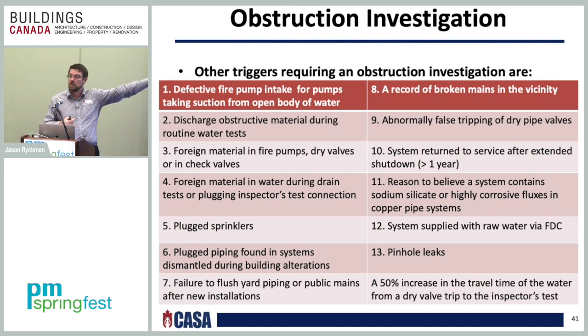If you have a record of broken mains within the vicinity of your building, that would be an obstruction investigation. Abnormally frequent false trip tests. So obviously with the dry system, if you have multiple trip tests for no apparent reason, that is a means of doing an obstruction investigation. System returned to service after an extended shutdown that is greater than 1 year, you have to do an obstruction investigation. Reason to believe a system contains sodium silicate or highly corrosive fluxes in copper piping systems. A system supplied with raw water via the fire department connection. Pinhole leaks.